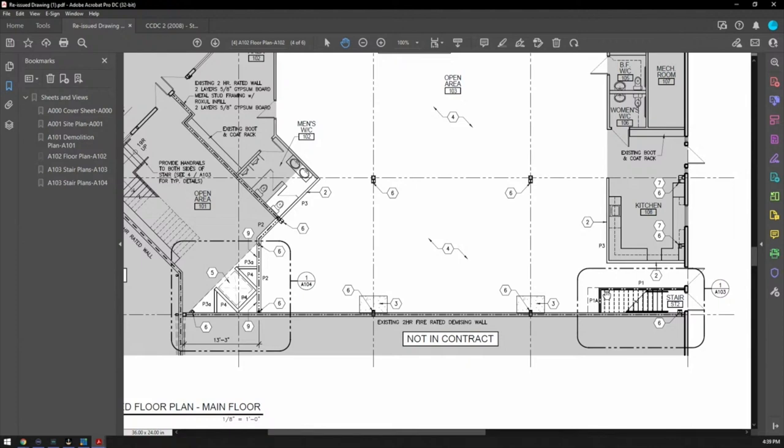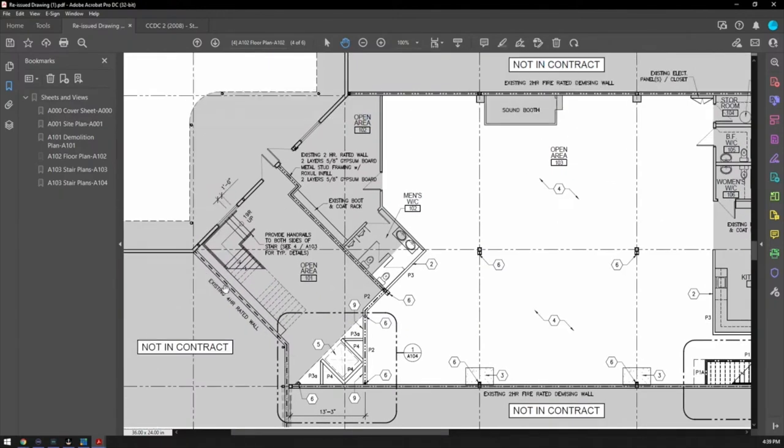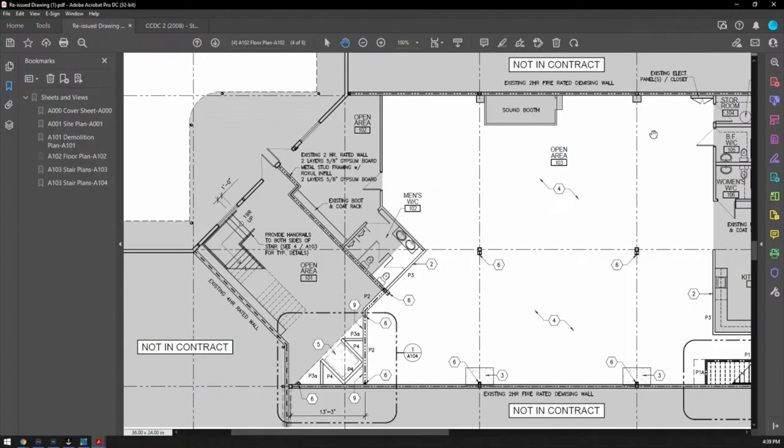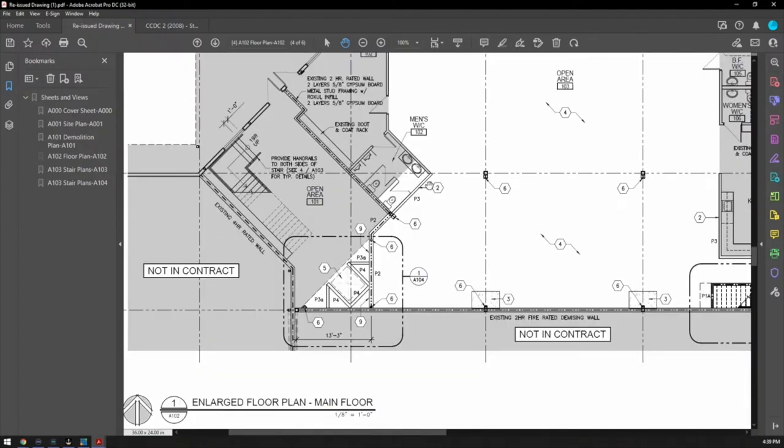This looks like that's for your one hour wall and then see on your four hour, long line and then a big space, long line space over here. Here's another two hour. Line, dot, dot. That represents your two hour wall, just double five-eighths type X, both sides. You can tell just by looking at the lines that that wall there has double five-eighths, both sides. Any wall here that is not fire rated doesn't have the lines, right? So you're good to go here.